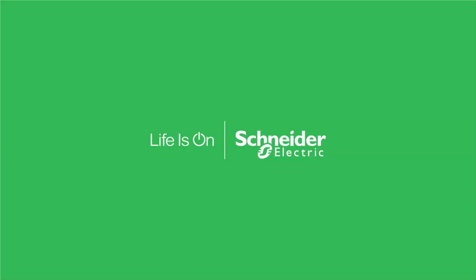Okay. How do I determine if my hospital's existing power distribution equipment has meters or intelligent devices that can be used in a power monitoring system? Yeah, and that goes back to the best practices. One of the first things that I said is to have a list of your assets and your meters and your smart devices. If you don't have that, or maybe you're new and this is a new facility for you, the best thing to do is to conduct a survey and to look at all of those strategic points that I'd shown: the normal mains, the emergency mains, the transfer switches, the medical equipment, and then where your energy consumption is very large, so your chillers and other equipment like that.